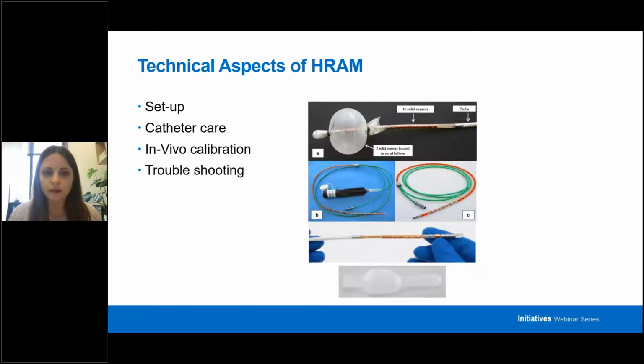It's very important to take good care of the catheters. The sensors are very sensitive, so avoid touching them as much as possible. With the Medtronic equipment we use in our office, when applying and tying on the balloon, we want to be delicate and not press on those sensors if at all possible. You can see these little silver markings here — those are not sensors, so you can touch those. That's usually what we try to only press on when tying the balloon onto the catheter.